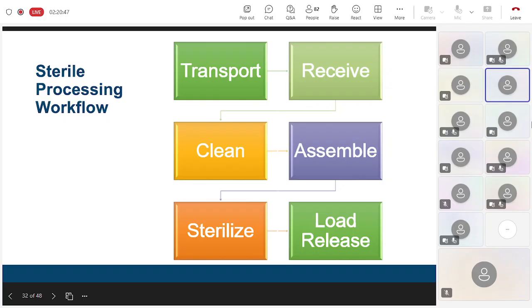Once the CSSD receive the device, the cross-functional implementation team should consider where the device will be received and what information should be delivered with the device. So we need to make sure that the trained staff who have demonstrated competency know exactly what is coming into the department, what needs to be cleaned, and what information is with it. Once we clean it, we assemble it, it is checked. It has to be checked so that there is nothing wrong with the device, nothing broken or deformed, and then we place it into the tray or the packaging material with a chemical indicator, and using the validated sterilization cycle parameters, we sterilize that device.